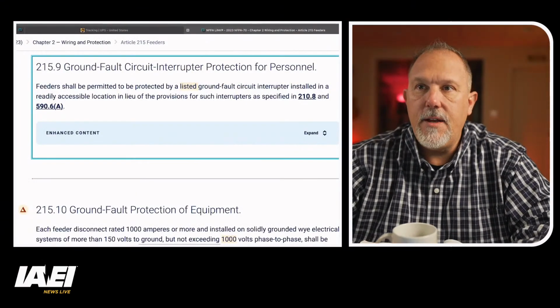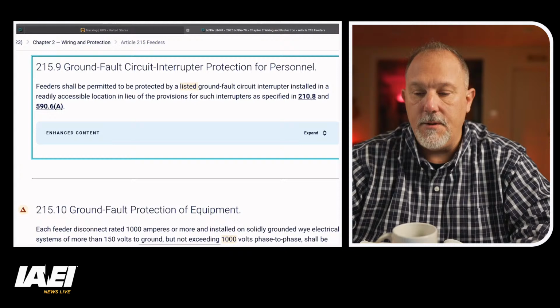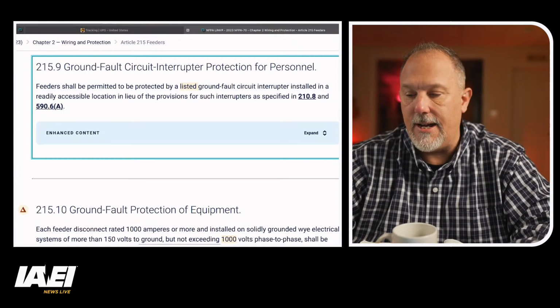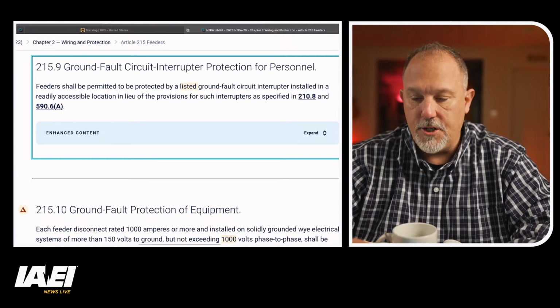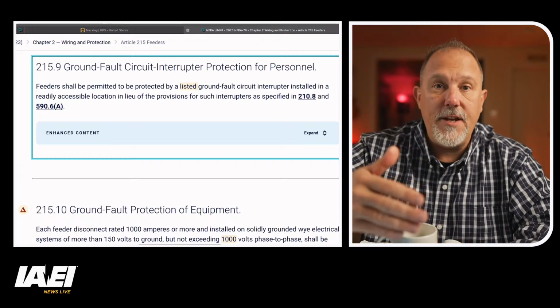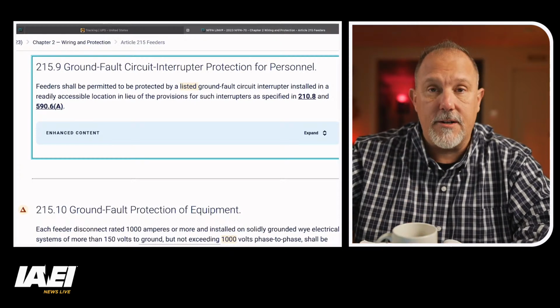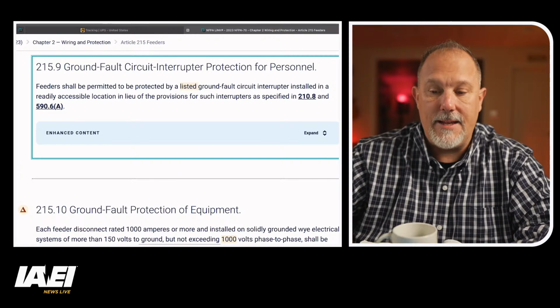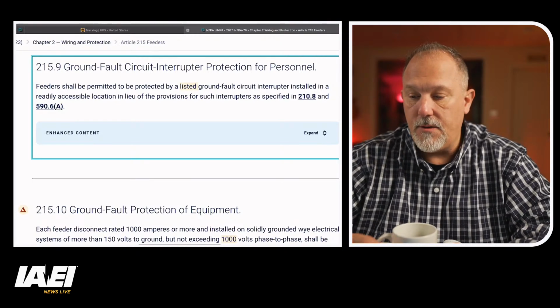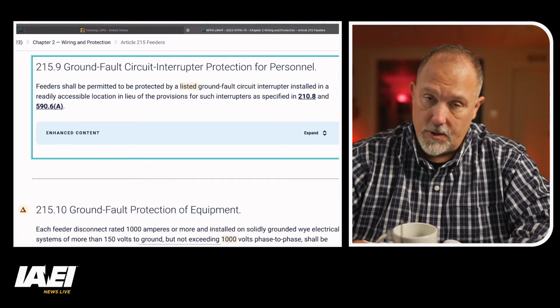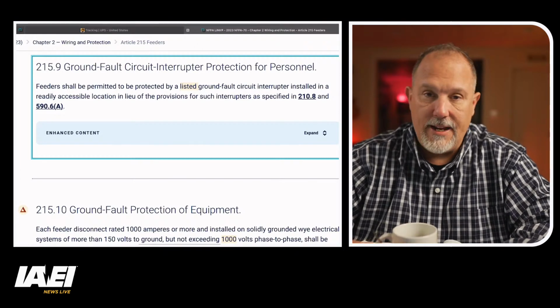Well, in 215.9 to be exact, it says you can put the listed GFCI in a readily accessible location and protect the feeder, which then protects all of the branch circuits that feeder supplies. And that is permitted to meet the requirements in 210.8 and 590.6.